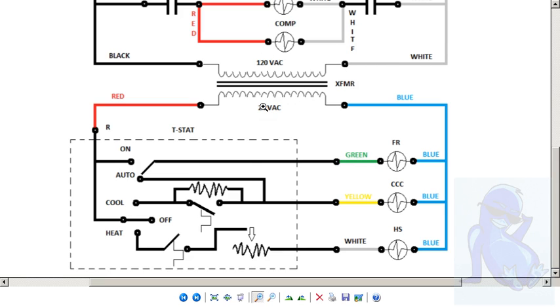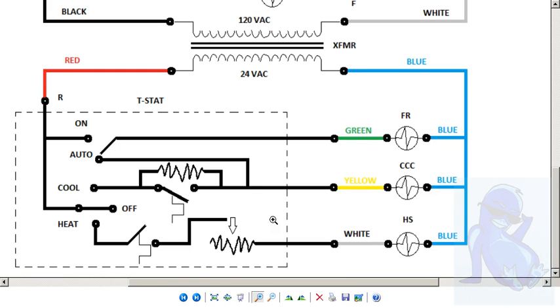This represents our transformer, step-down transformer from 120 volts to 24, and our L1 to switch. And in this case, this whole dotted box here, this is the thermostat. See, the thermostat is just a complicated switch. This is set for either auto or on. Here's your switch for auto or on.